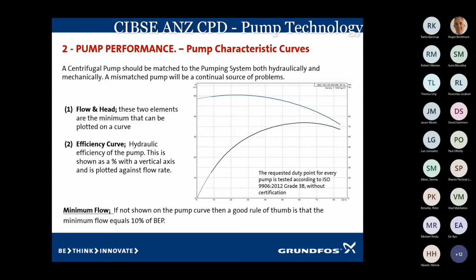No, it won't work. The blue curve is the performance curve, and if you follow that, you can see at the top left-hand side it reaches 50 meters, and out to the right-hand side it drops down to about 35 meters. The performance curve is what we expect the pump to work to, depending on the flow rate. If we have a look at a flow rate of 70 litres a second, and we take that vertically up, where it hits the performance curve, we go horizontally across, and we can see that pump will produce about 42 meters head.